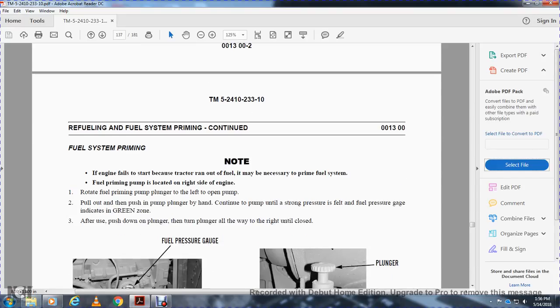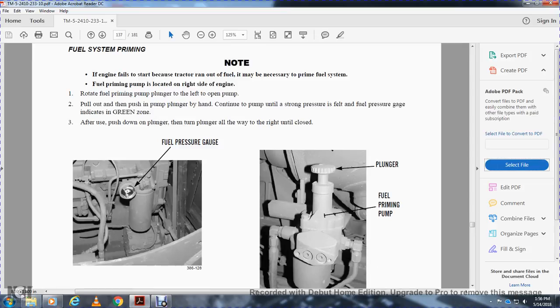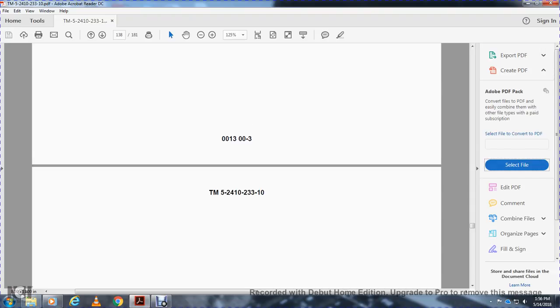Fuel priming. If the engine starts to run out of fuel, it may be necessary to prime the fuel system. The fuel priming pump is located on the right side of the engine. Rotate the fuel priming pump plunger to the left to open the pump, pull up, and then push the pump plunger by hand. Continue pumping until strong pressure is felt and the fuel pressure gauge indicates green. After using, push down the plunger and turn it all the way to the right to close. Fuel pressure gauge, plunger, and fuel priming pump. End of work package.